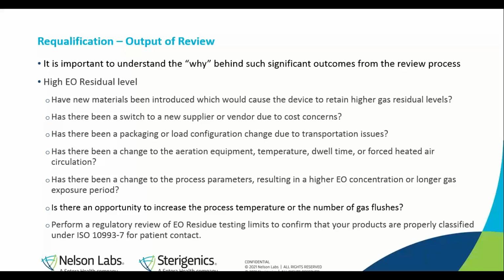Has there been a change to the aeration equipment, including the temperature, the exposure time or dwell time, or forced heated air exchanges? That would have an impact on product residues. Has there been a change to the process parameters, resulting in a higher EO concentration or especially a longer exposure period? Is there an opportunity here to increase the process temperature or the number of gas flushes at the back end of a cycle, which would be designed to remove EO from the product within the chamber? Lastly, I would suggest performing a regulatory review of EO residue testing limits to confirm that your products are properly classified for patient contact under the standard ISO 10993-7.